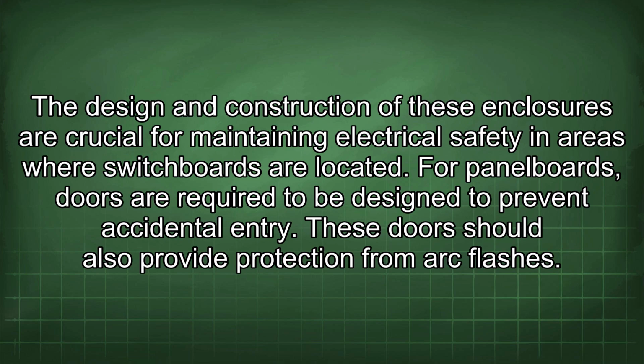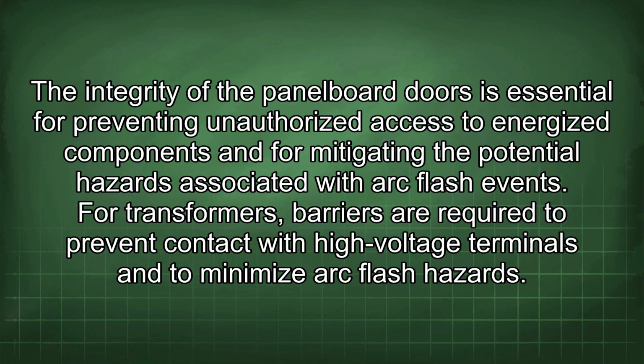For panel boards, doors are required to be designed to prevent accidental entry. These doors should also provide protection from arc flashes. The integrity of the panel board doors is essential for preventing unauthorized access to energized components and for mitigating the potential hazards associated with arc flash events.